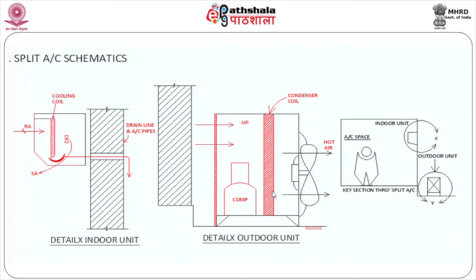With the window air conditioner, there was a constraint that there was no distance between the hot end and cold end. Here you can have a small distance between the cold end and the hot end. It can even be one room apart because the connection is by refrigerant pipes. These pipes have a limitation. Ideally, they should not exceed 5 meters. Now, this was as far as a basic split air conditioner is concerned.